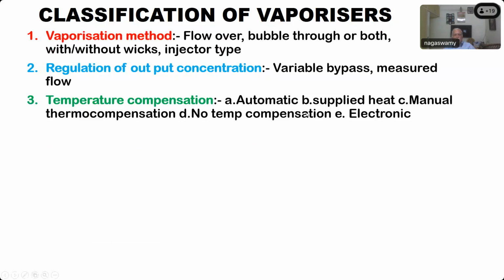All the older ones, Boyle's bottle, the Goldman vaporizer, which I showed you in the last class, all of them do not have temperature compensation. So the output is not constant. It will vary according to the ambient temperature. Whereas the modern vaporizers are all automatically set to deliver the accurate concentration by supply of heat, and the latest is by the electronic method.